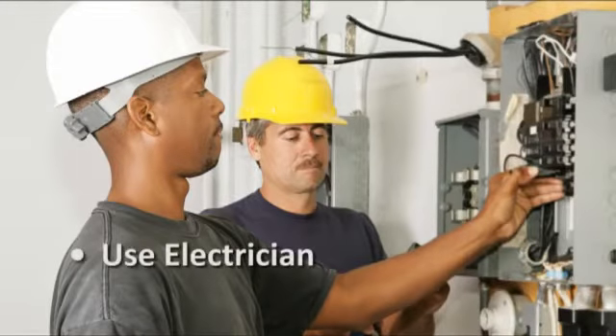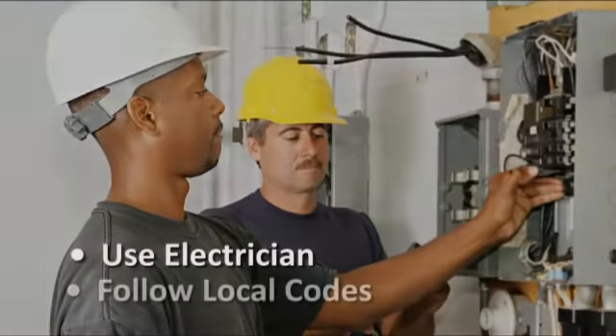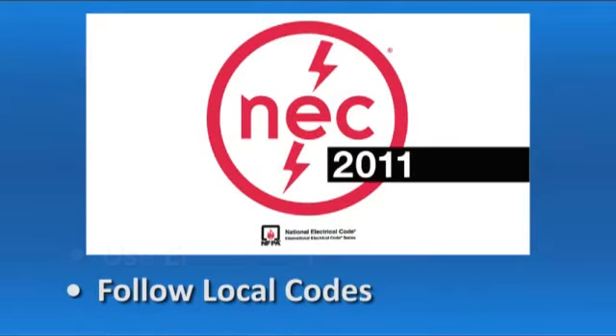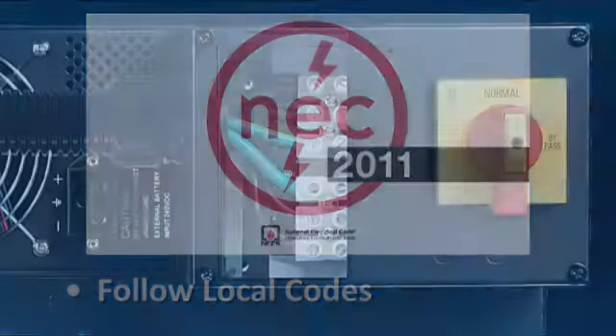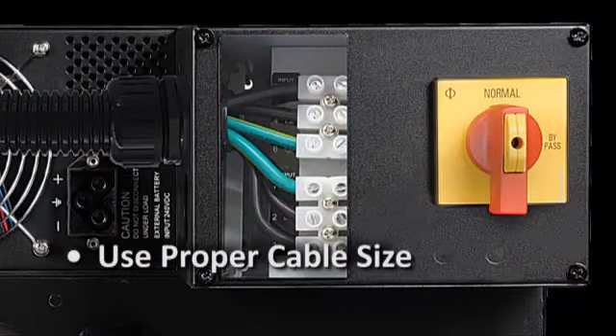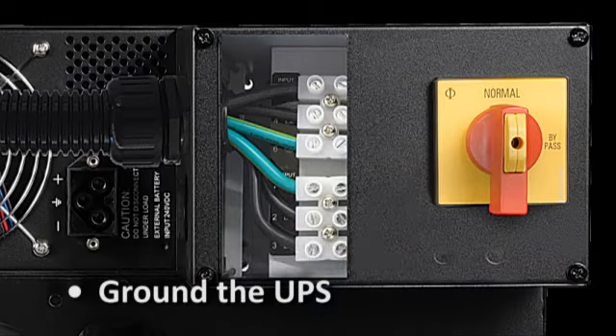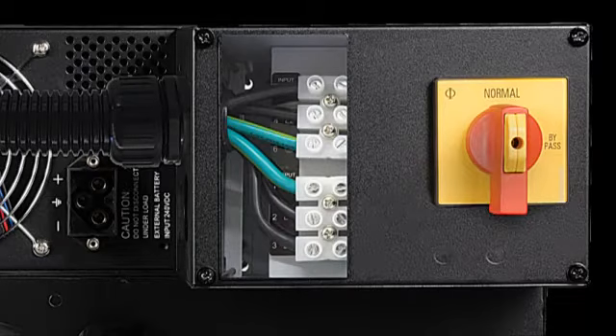Wiring must be done by a qualified electrician. When making wiring connections, electricians should observe the cable connection regulations appropriate to your area, for example, the National Electrical Code, NEC, in the U.S. Ensure that cables are fitted with cable sleeves and are secured by connector clamps. Make sure that your equipment is properly grounded. Using cables of improper size may damage your equipment and cause fire hazards. Choose appropriate cabling and protection circuits to make wiring connections. Ground conductors must be the same size and power type as the conductors used.